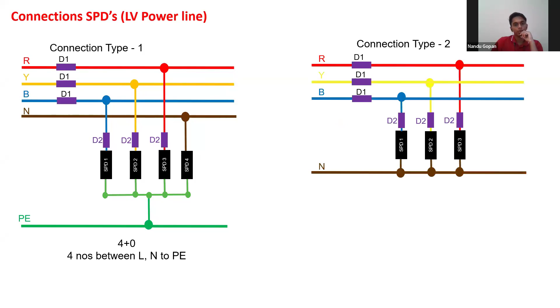The next type of connection is 3 plus 1. There will be three lines of SPD connected to neutral, and one connected to PE. For a TT system, you are supposed to go with this 3 plus 1 connection. And for a TN-S system, you can go with either one. Maybe you can go with the type 1 connection. But for TT, the earth electrode earthing system, you are supposed to go with type 2 connections. And also, if there are any over voltages, in type 2 only one SPD will play, but here all the SPDs will fail if there is any over voltage. But anyway, I'll not be explaining that much.